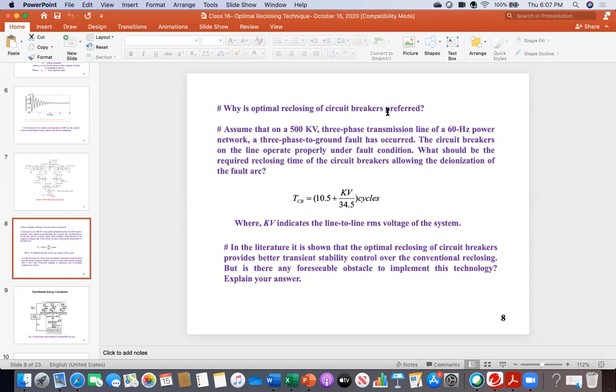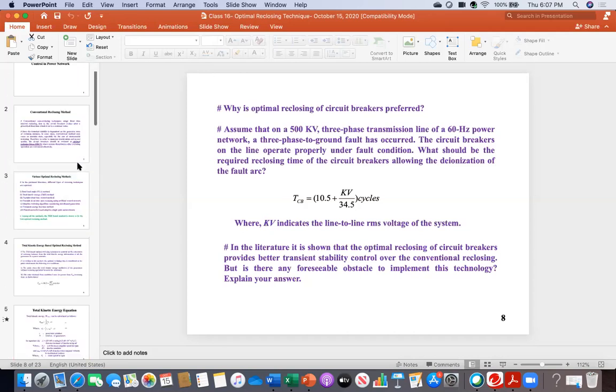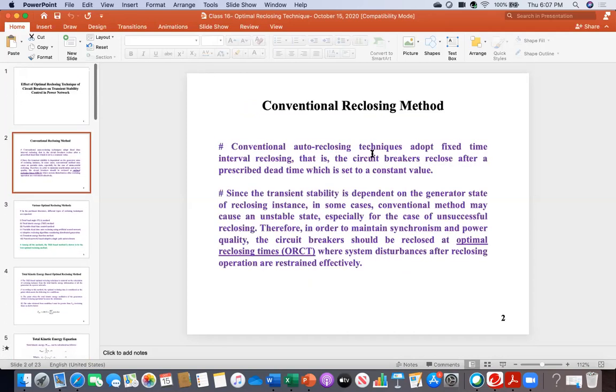Sir, does conventional mean manual reclosing? No, that is also auto reclosing, but at fixed time. Conventional auto reclosing techniques are automatic, not manual, but adopt a fixed time interval for reclosing. Meaning, as I showed on the whiteboard, the circuit breaker opens, and then it waits exactly until that fixed time.